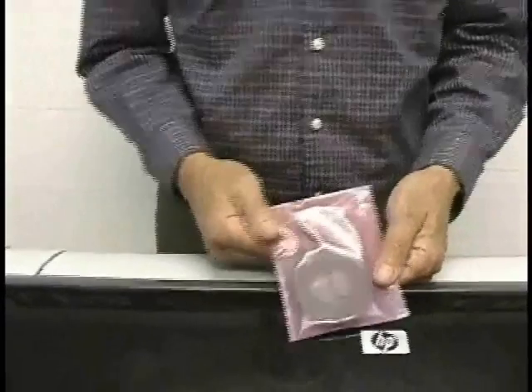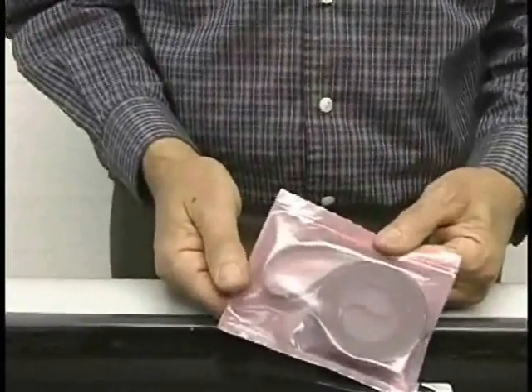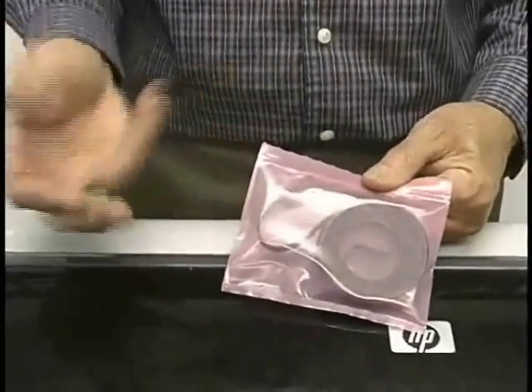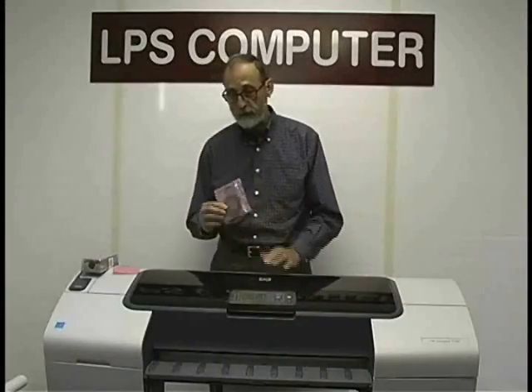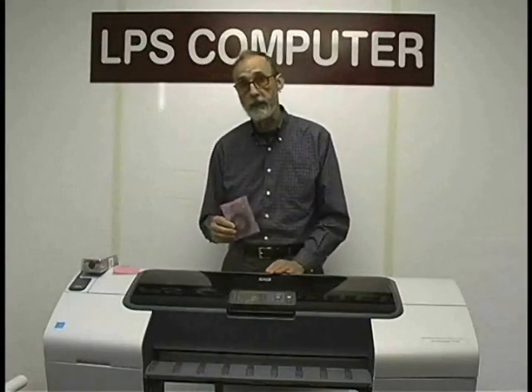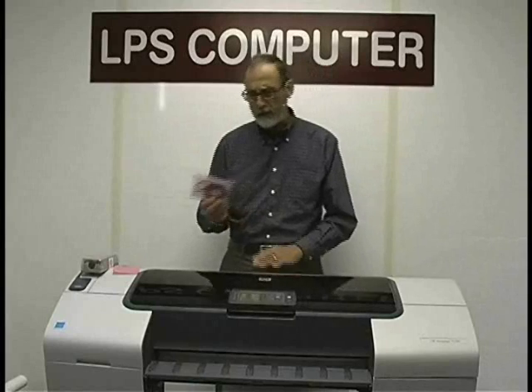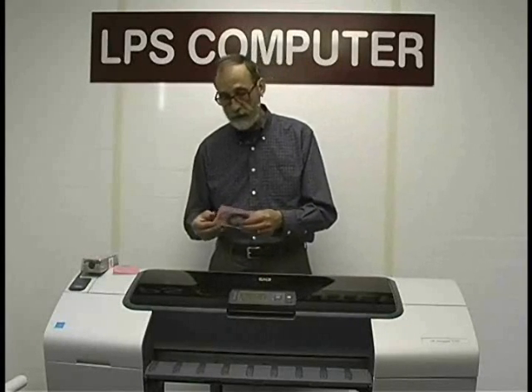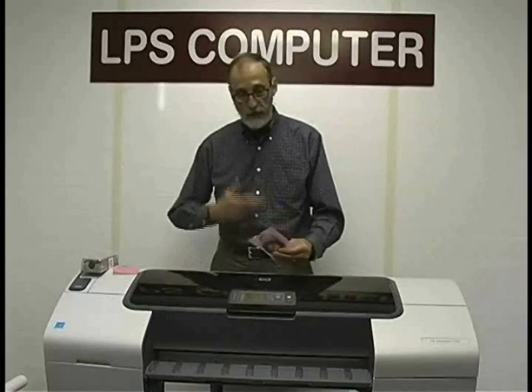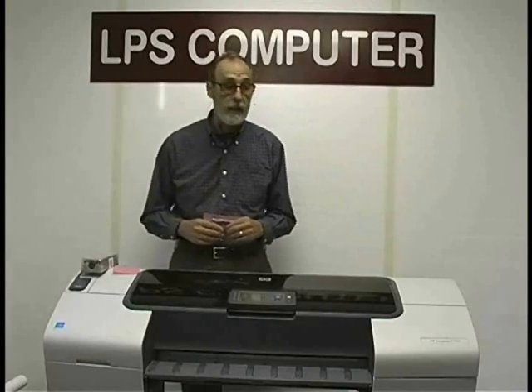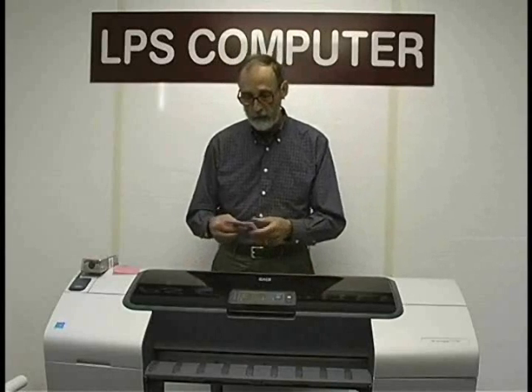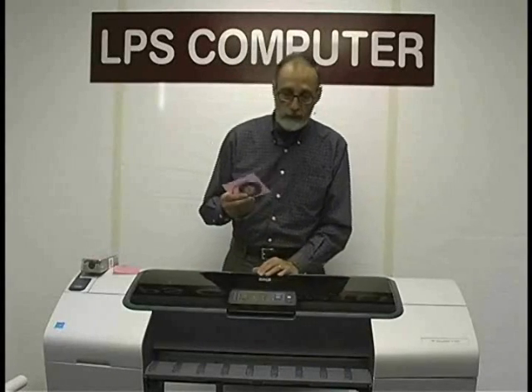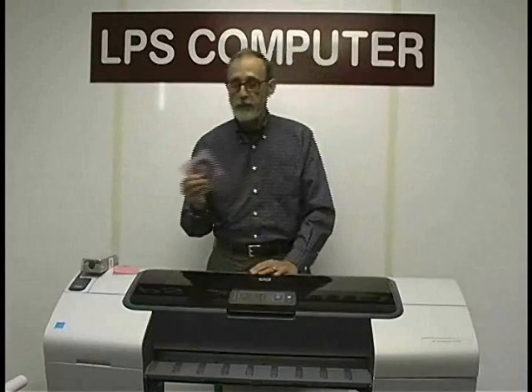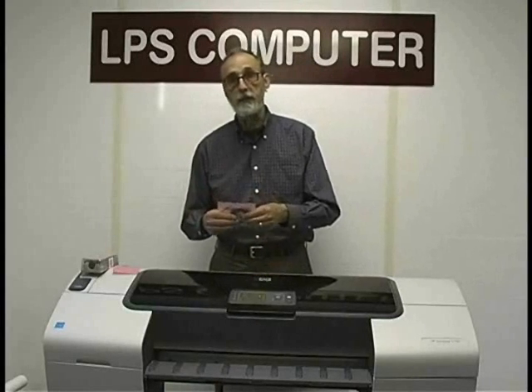These belts use the latest technology, the latest materials. The black material is high density polyurethane. I don't know for sure if the OEM uses an anti-oxidant or not, but ours does. These belts tend to oxidize over time, and I know about after about 5 years the OEM will start to disintegrate. We've only been making these belts for 4 years, so we don't know if it's going to go longer than 5 years or not, but so far so good.